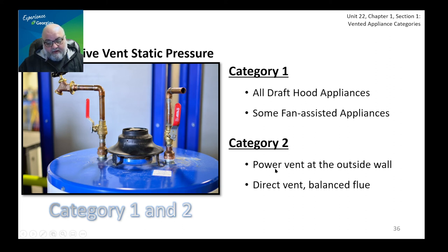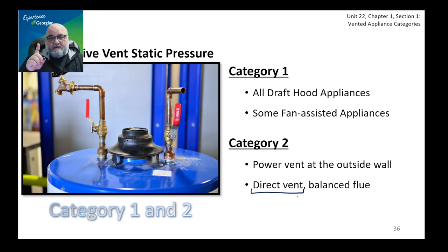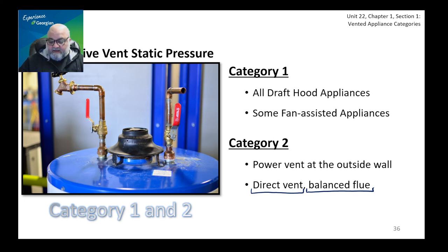Category two is a power vent at the outside wall — interesting because the power vent or venter motor is not an integral part of the appliance itself. It is an add-on component installed at the outside wall. There is also direct vent, where all combustion air comes from outside and all combustion products go outside without a venter motor, using a balanced flue. It's an engineering marvel, but that's why you don't see many category two appliances — they are difficult to design. There are a few commercial/industrial boiler types that are category two.